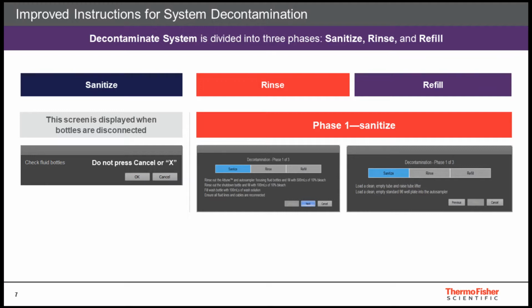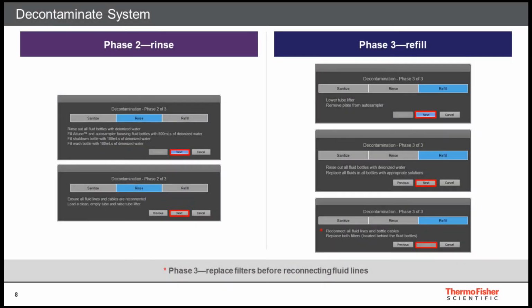For the first part of the script, about 700 plus mils of bleach solution is required. In addition, 100 mils of wash solution needs to remain in the container to continue. In phase 2, 10% bleach solution is replaced with ultra-pure water to flush out the bleach. About 800 mils of water is needed. In phase 3, replace DI water with appropriate normal operating solutions and replace both focusing fluid filters.